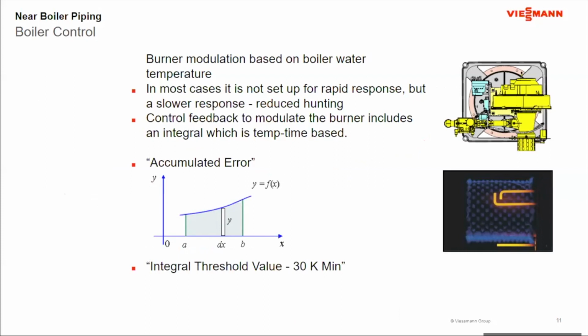Now, heat loss within a building does not rapidly change load. If I look at a building, the outside temperature doesn't all of a sudden, in 15 minutes, go from 45 degrees Fahrenheit down to 15 degrees Fahrenheit. That happens over long periods of time, so you have a load that tends to change slowly.